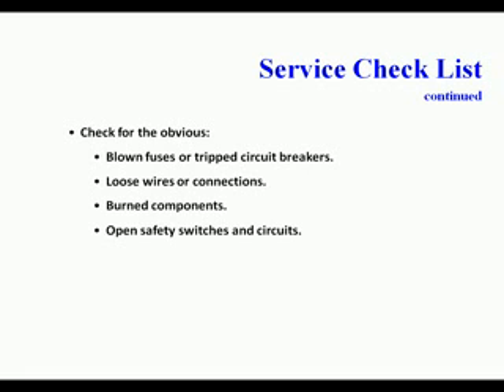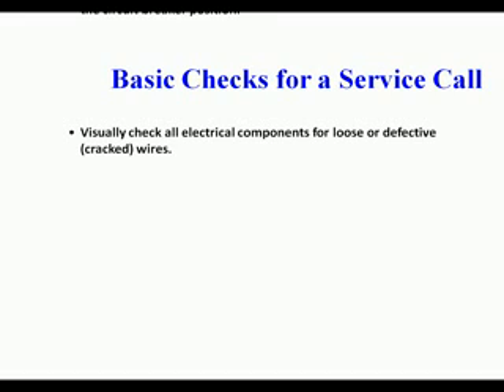What you want to do is check the general condition of the furnace and the surrounding areas. Things that can cause problems include lack of combustion air, improperly sized vents, poorly or non-functioning air filters, or electrical shorts due to a water leak in evaporator coils or humidifiers. Check the obvious first. Look for blown fuses or tripped circuit breakers. Find loose wires or connections. Look for burned components and open safety switches and circuits. Check the manufacturer's instructions. Observe sequence of operation. Confirm correct wiring, and check self-tests and fault code LED functions.